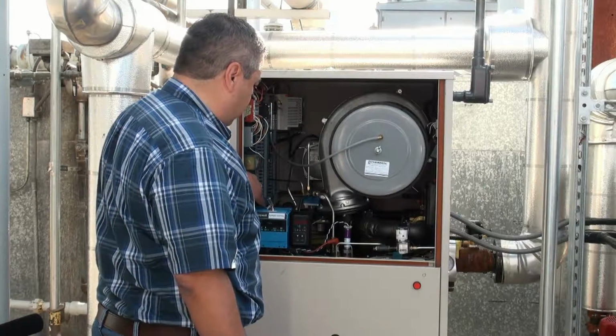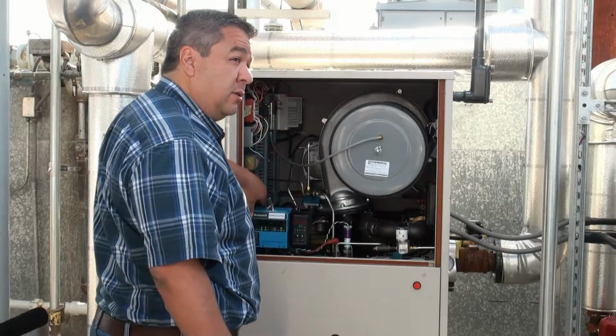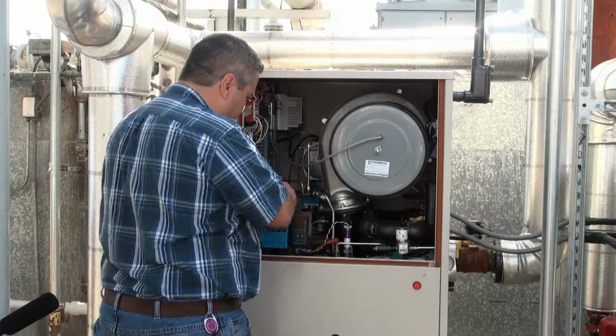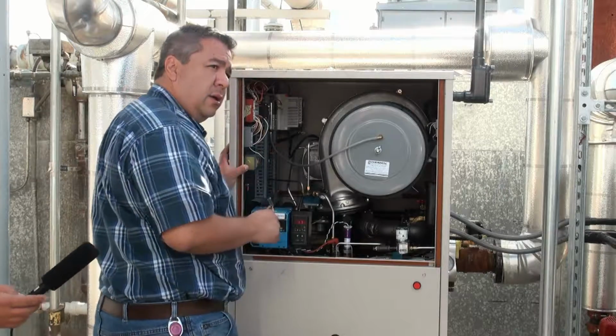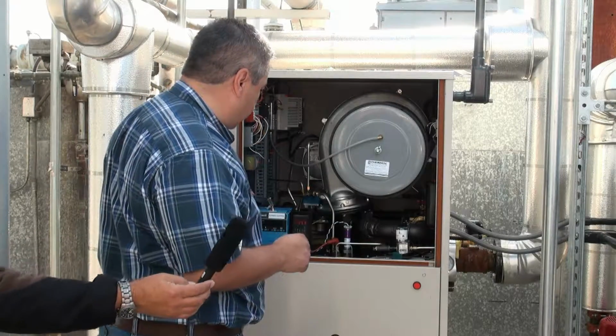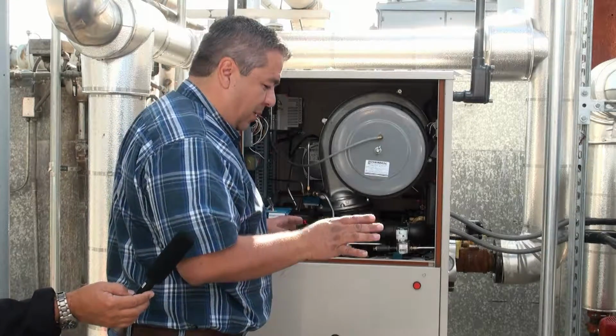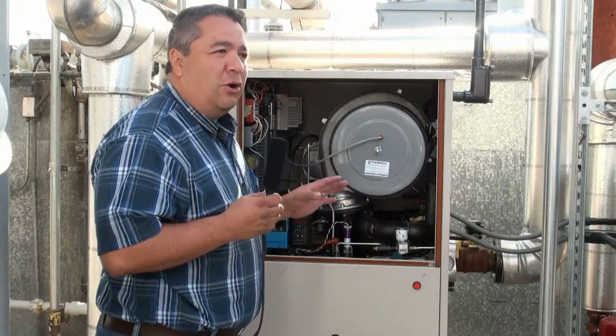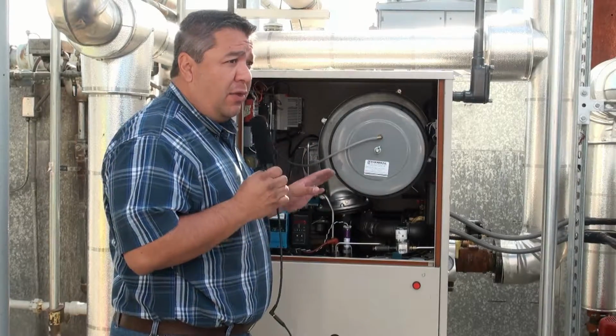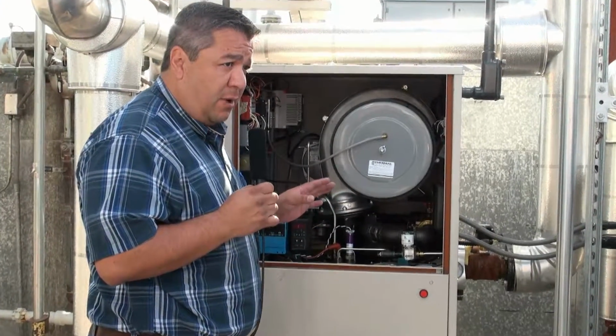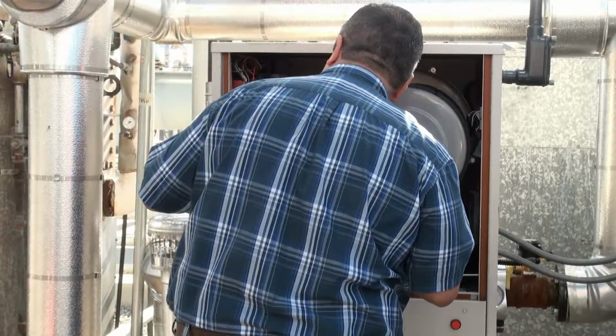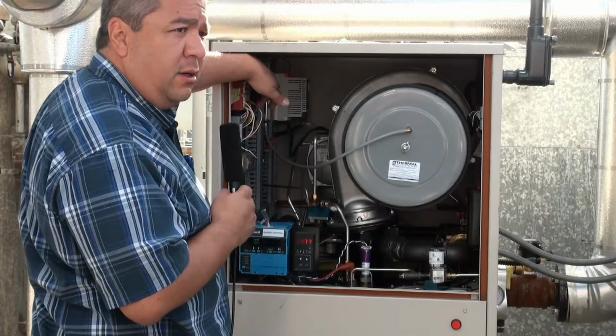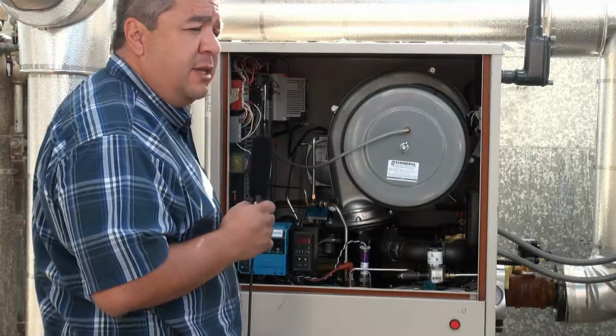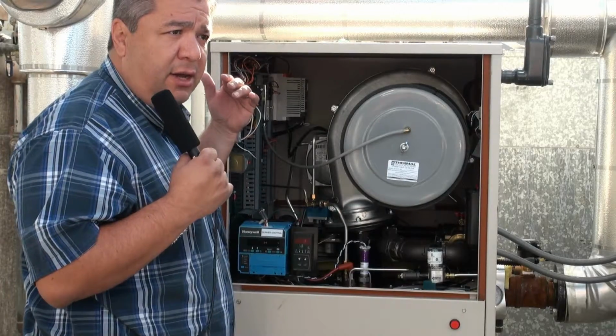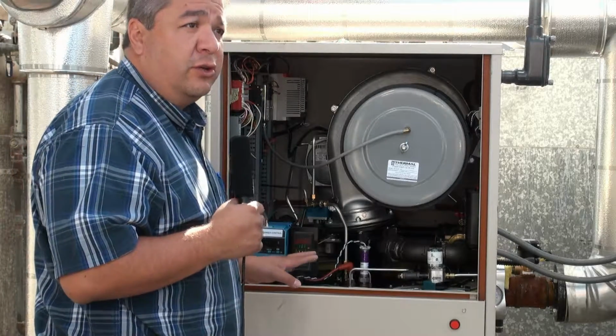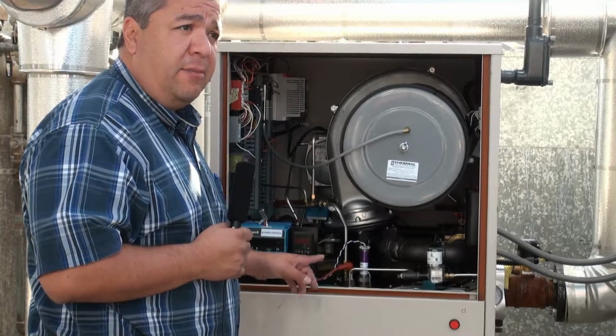Where does the start-stop signal come in? It comes from the controls. Can you show where it's landing? It's actually a Modbus, into this controller right here. So if I don't want that signal coming in, or I want to jump it out and make it start up, how do you do that? So it's in Modbus set point control - he's enabling and disabling the boiler through Modbus. In order for that not to happen, you'd have to remove this jumper right here.